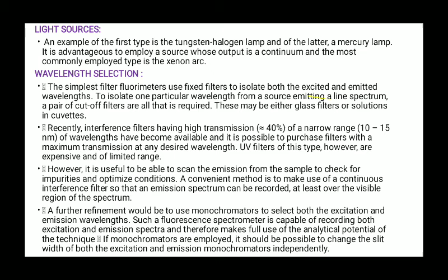The material from which the photocathode is made determines the spectral range of the photomultiplier, and generally two tubes are required to cover the complete UV visible range, because the beam present in that spectrometer is UV light, right? So the requirement is that you need to cover the complete UV visible range, right? The S5 type can be used to detect the fluorescence out to approximately 650 nanometer.